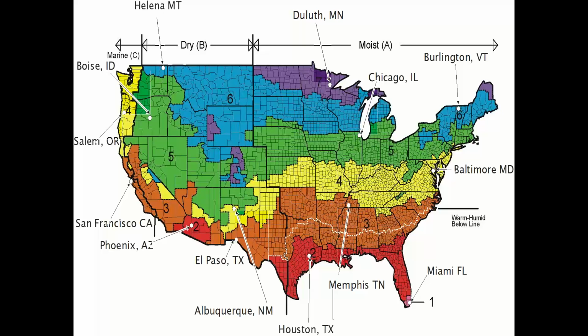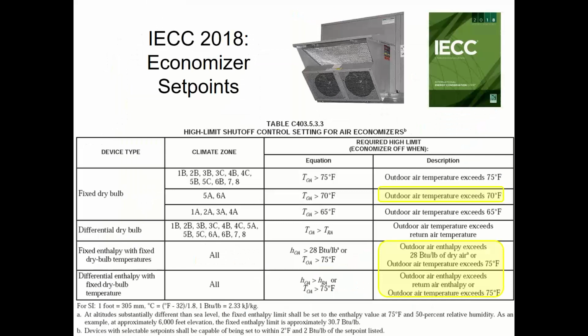All right, so 5A, my mouse locked up. That's not good. Well, if you're in 5A or 6A, as soon as my thing responds, there we go, you'll be on this line right here. So if you have a dry bulb sensor for 5A and 6A, you're required by law to set it for 70 degrees, meaning if it's less than 70 degrees, you have to use the economizer. If it's above 70 degrees, you do not use the economizer.